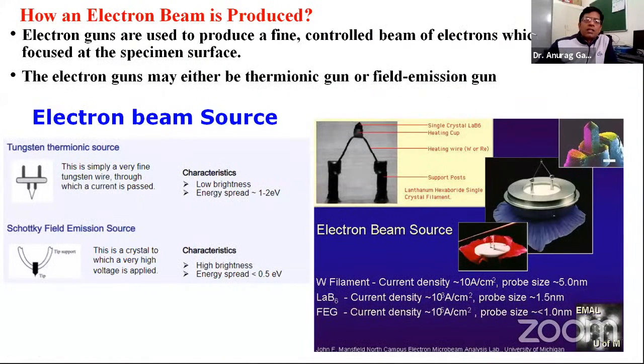As a source, I told you about the electron beam source. Generally two types of source are used in electron microscopy. The electron gun is used to produce a fine controlled beam of electrons, which are then focused at the specimen surface. These electron guns may either be thermionic or field emission based. The first is the tungsten thermionic source. This is a simple, very fine tungsten wire, and we pass current over it. By passing the current it heats up, and by thermionic emission the electrons are emitted. These electrons are accelerated by applying a voltage at the anode.